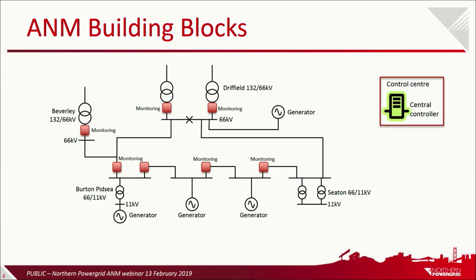And we've also installed a central controller at our control center, which uses the real-time monitoring information in its network analysis to determine whether any transformers or circuits are approaching the limits of their capability. So this is the central controller, that's one of the big ticket items, if you like, with regards to shared costs. We've touched on the monitoring equipment, so the monitoring equipment can be a combination of both shared and sole use, dependent on whether a customer is contributing towards a particular constraint or not. But the central controller is the big ticket item for a shared cost, if you like.